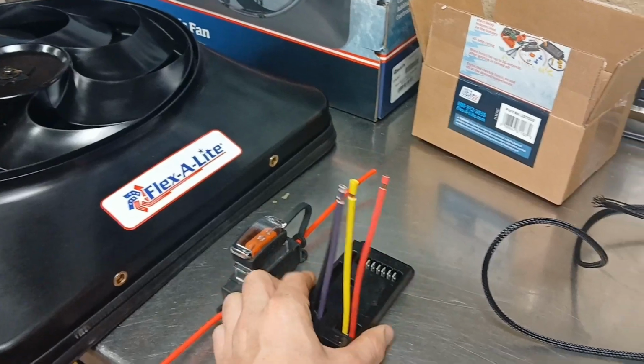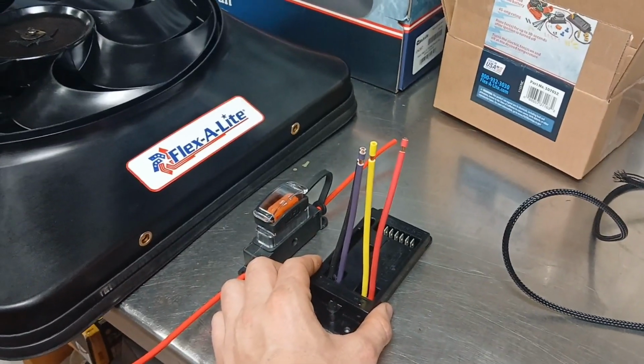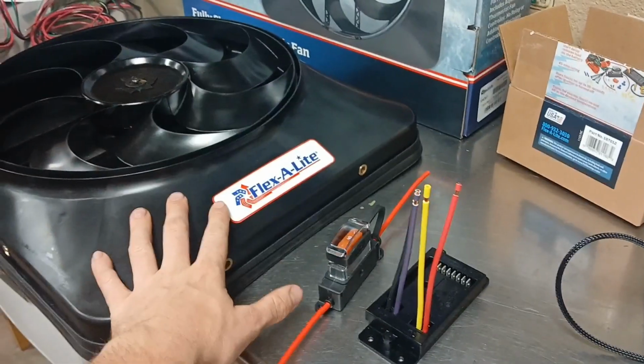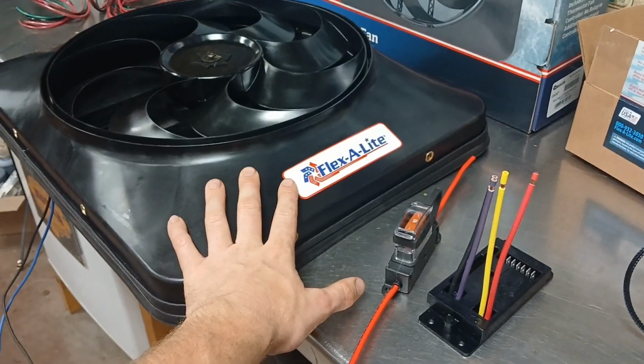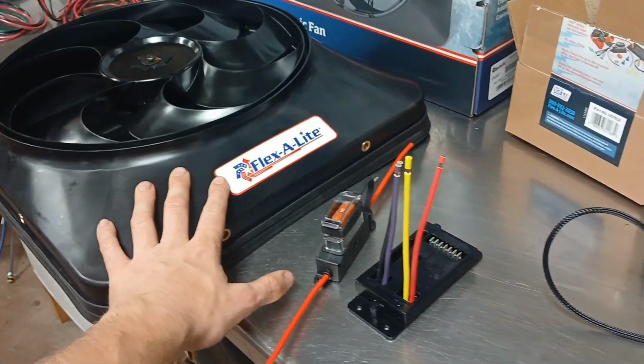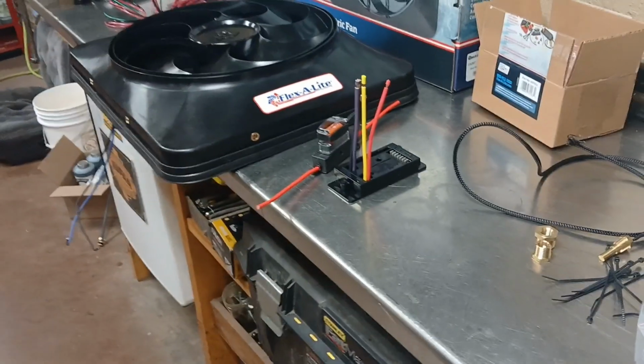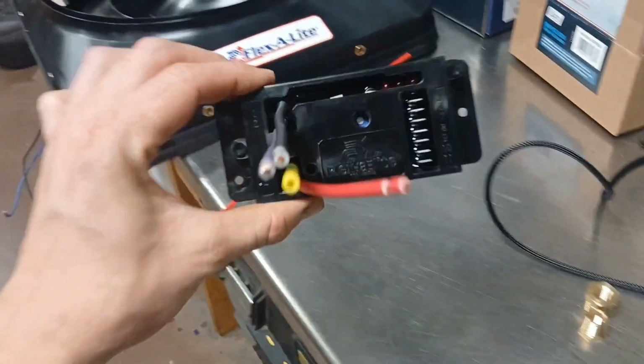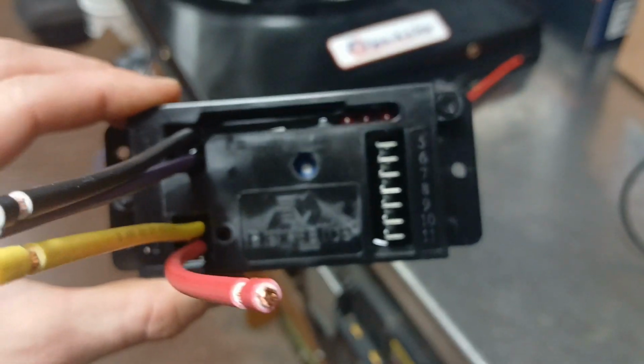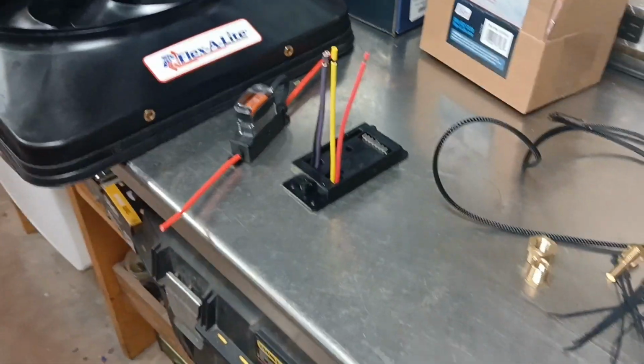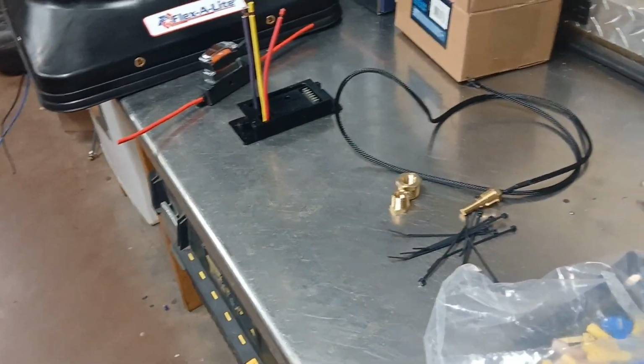This pulse width modulated fan controller will toggle this fan on starting at 60% and will cycle up to 100% depending upon what the coolant temperature is. It does have a little adjustable screw in there, so you can dial in the temp setting for where it turns on and off at.